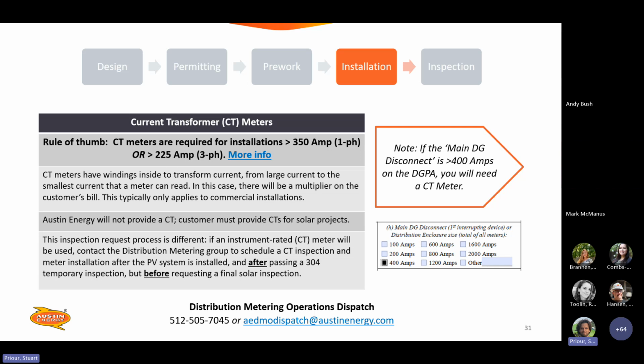If we can look at that switchgear de-energized and ensure that it's wired properly, then we'll pass the 304. Actually, that in itself is not the step that initiates the metering team to go out there. So we'll pass the 304 with you guys, and then the contractor is responsible for sending an email to AE DMO dispatch at Austin Energy to request that the CT inspection happens. So that's 304, CT inspection, then the 305.